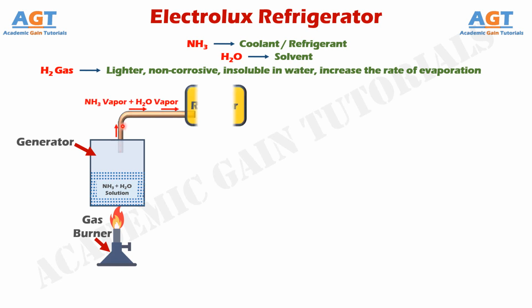After that, this vapor of ammonia and a small amount of water vapor will leave the generator and enter the rectifier through this connecting pipe. The rectifier can also be called a water separator. When vapor of ammonia is formed here in the generator, there will also be some proportion of water in it. That is, through this connecting pipe we will have ammonia vapor and some H2O or water vapor particles coming into this rectifier. Now, the rectifier separates these water vapor particles from the ammonia vapor. After being separated, these water particles accumulate here in the rectifier, and then the rectifier sends this water back to the generator to be reused.